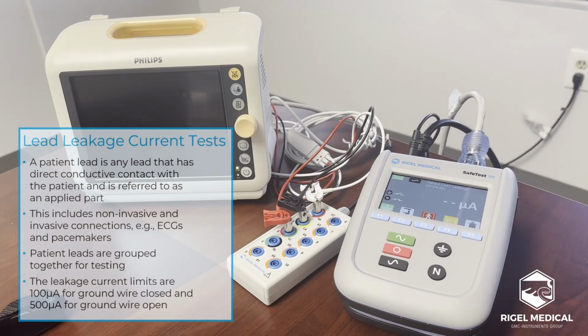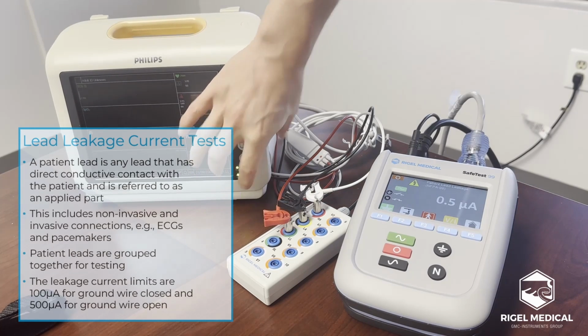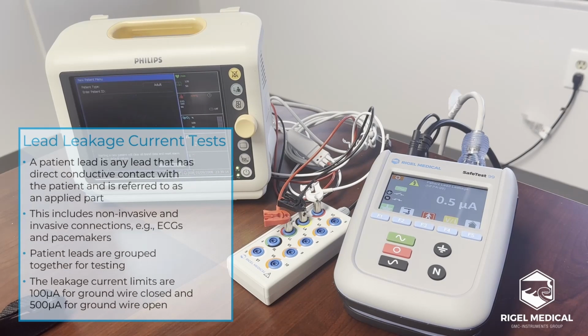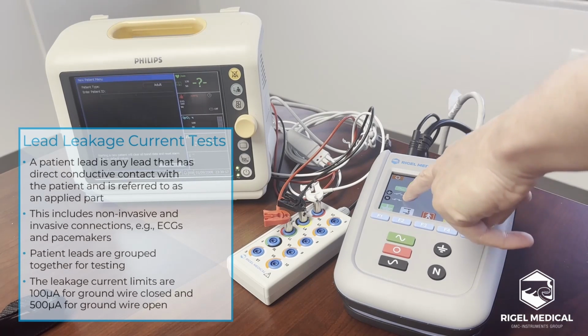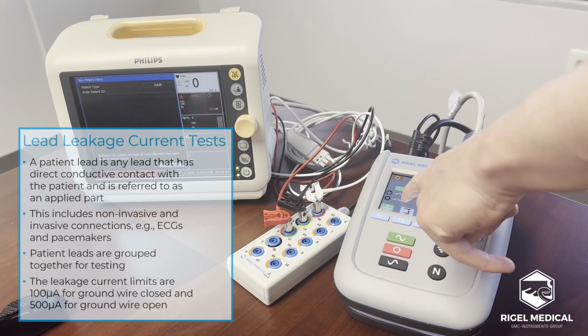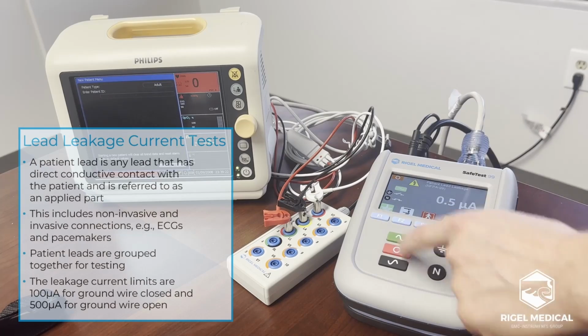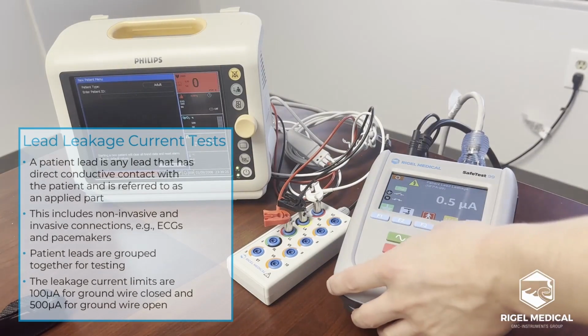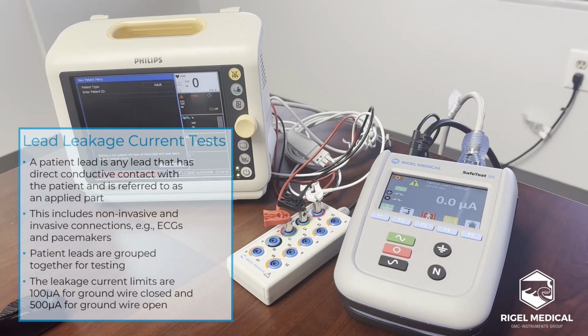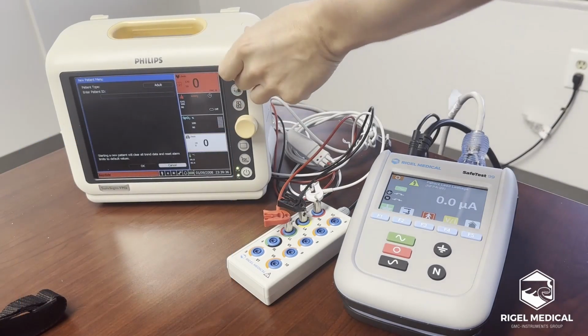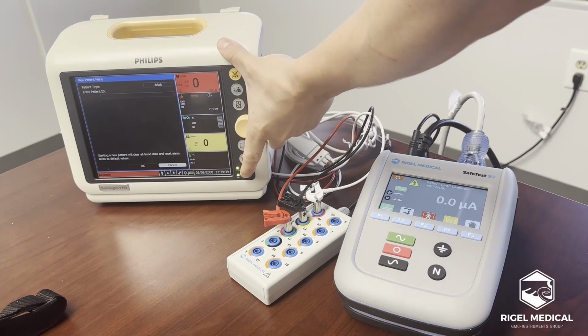So again, hit the green button. Device switched on. And we've got ground wire open from the previous test already. So ground wire open, we've got a limit of 500 microamps. And then ground wire closed. So we've got 100 microamp limit there, well within the limits of NFPA 99.